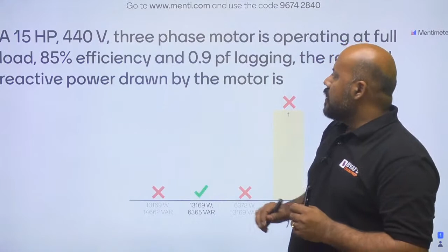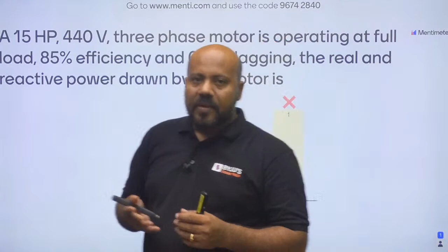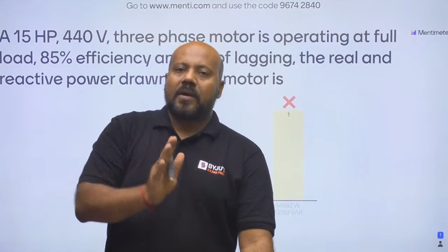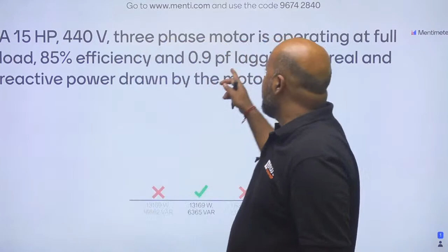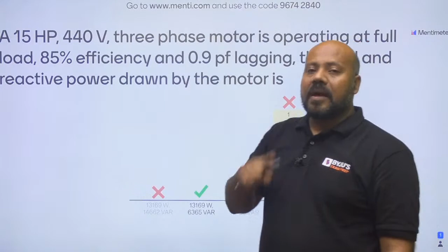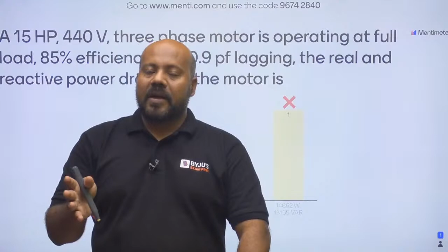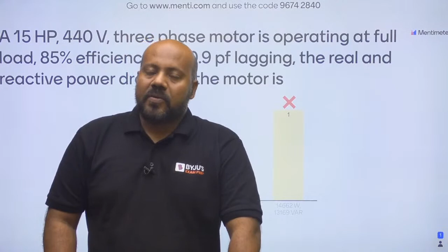He is also giving you the power factor. If you know the power factor, you know the power factor angle. Yes or no? And you know the relation from the power triangle: P, Q, and the resultant is the complex power. And the angle between the apparent power and the real power is the power factor angle. From here you can find the power factor angle, cos inverse 0.9. And now you can establish the relation: reactive power is equal to real power multiplied by tan phi. In the power triangle, you can simply apply tan phi and you will get the relation between P and Q, real and reactive power. So you have already calculated real power, you can easily calculate the reactive power.